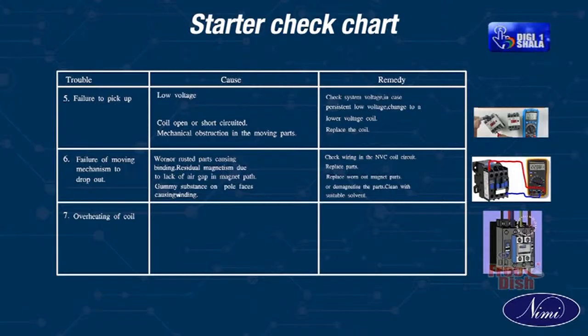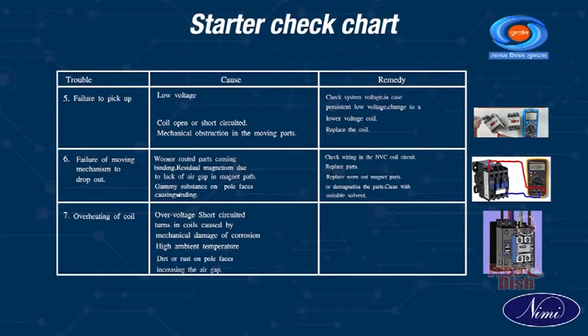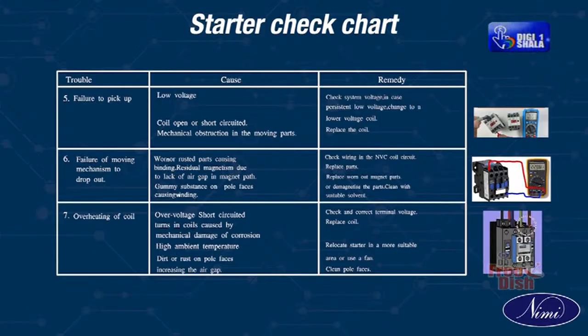Overheating of coil. Cause. Over voltage, short circuited turns in coils caused by mechanical damage or corrosion, high ambient temperature, dirt or rust on pole faces increasing the air gap. Remedy. Check and correct terminal voltage, replace coil, relocate starter in a more suitable area or use a fan, clean pole faces.